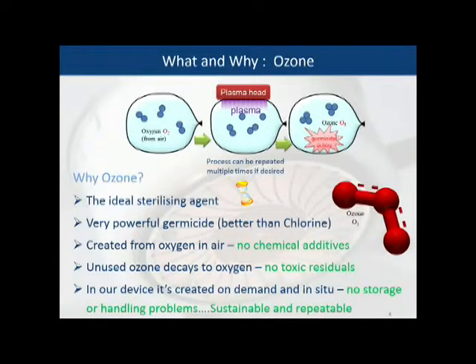And what we're doing is basically taking the oxygen, it's inside a sealed container, and using our plasma electrode from the outside, breaking down the oxygen into its individual state, and then that recombines to ozone, and that causes a germicidal effect inside the plastic bag. And I have to emphasize here, we're not adding any chemicals at all to the package. We're not breaking the seal of the package. All we're doing is breaking down the oxygen of the air inside that container and turning it into ozone. So from a sustainability point of view, we're not introducing gases, and that has obviously consequential effects. So it's sustainable and repeatable and much easier to handle than any other form of ozone.